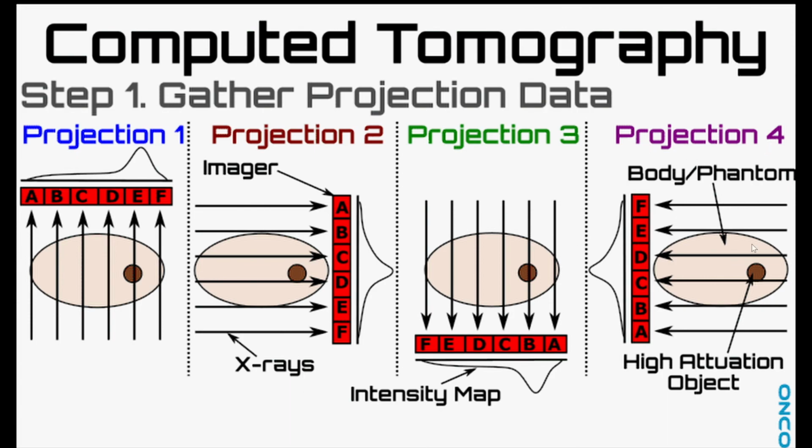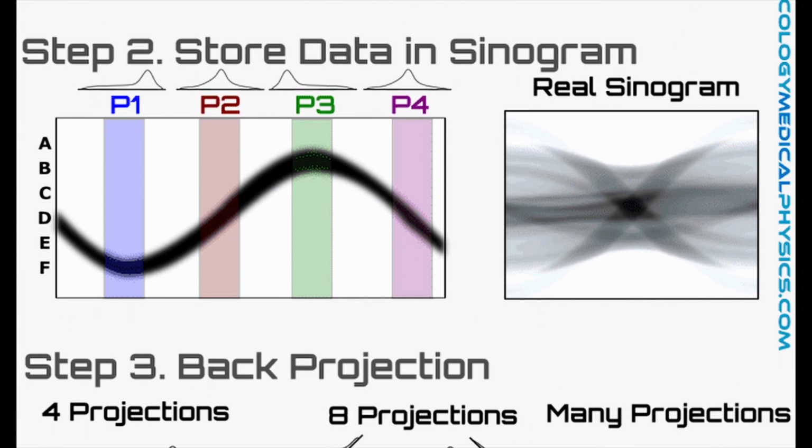And again through projection number 4, shooting through from the right hand side into the detectors on the left, and we get this response here from the detectors. Okay, at this point then, all the data that is collected is stored in a file called a sinogram, and this represents the four main views that we've just taken: position 1, position 2, position 3, position 4, and it traces out a diagram like that. Of course, there are readings taken in 1 degree increments right throughout the whole scan.